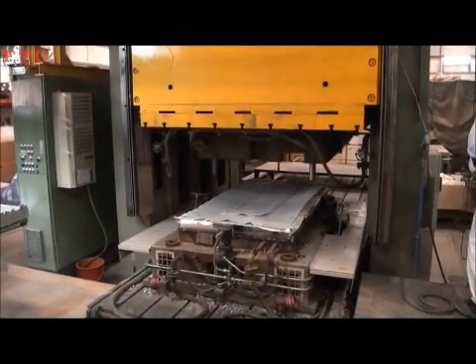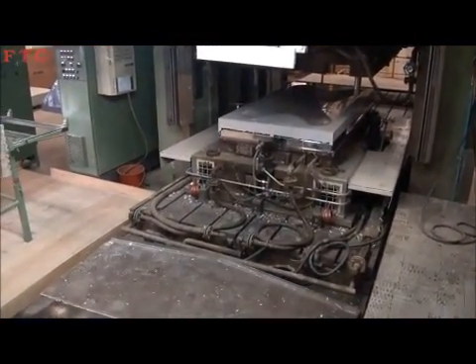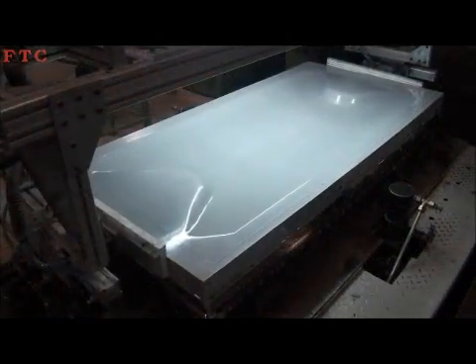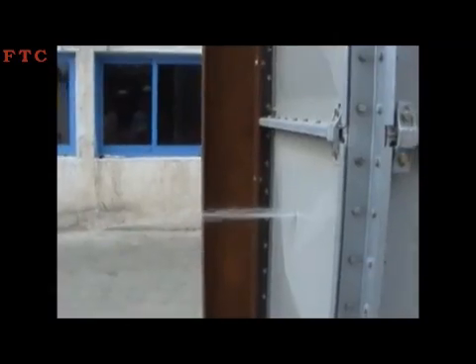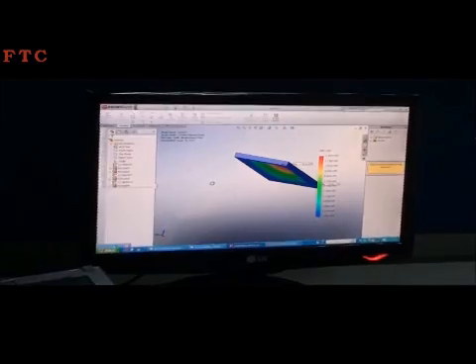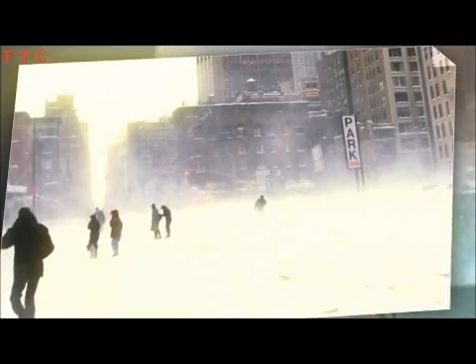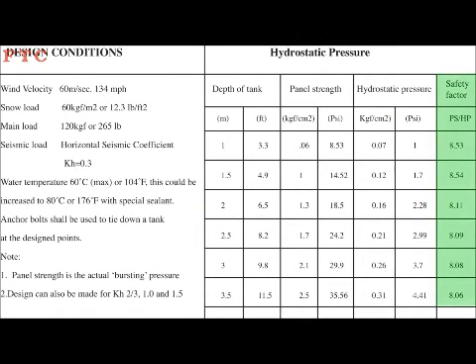On the other hand, FTC's hot press molding production process ensures zero defect and delivers high-quality panels with constant fiberglass distribution into the laminate with the most accurate dimensional stability for utmost reliability and performance. Fiberglass roving mesh is used on the external panel surface to enhance the tensile, flexural and shearing strength and to eliminate the risk of crack propagation. The panels are computer designed using finite element analysis for optimizing stress distribution and performance during earthquakes, high winds and extreme temperature changes, guaranteeing a massive eight-time safety factor of panel strength over maximum anticipated loads, proof against the worst natural disasters of the last 100 years.